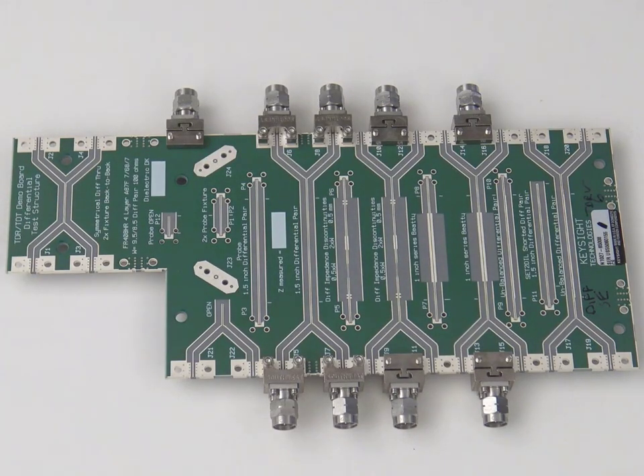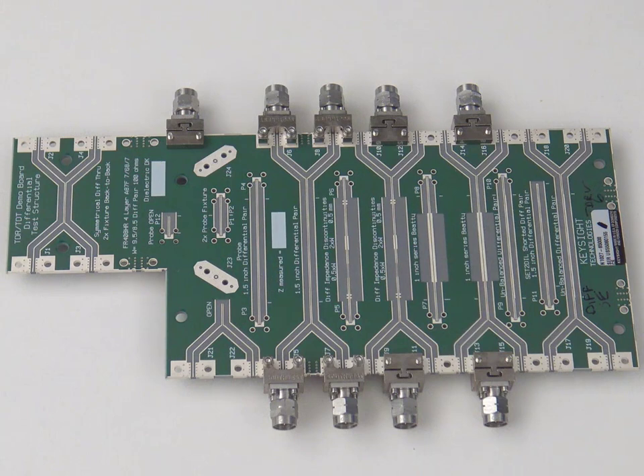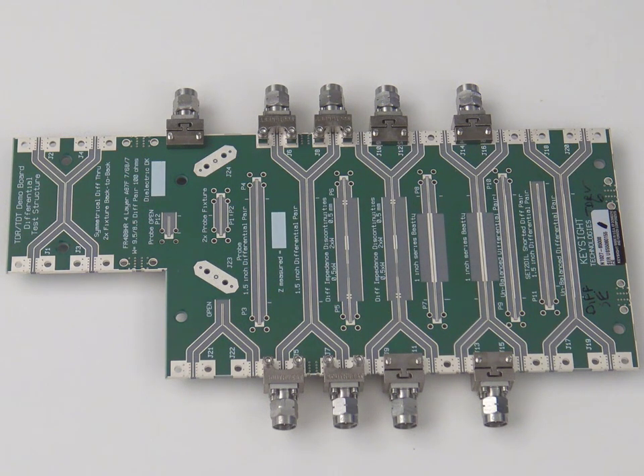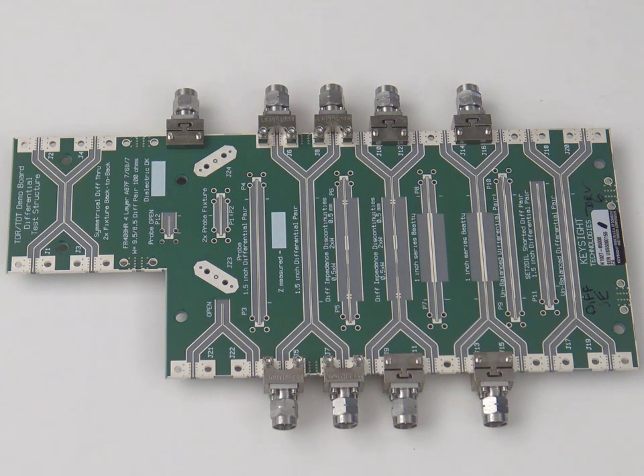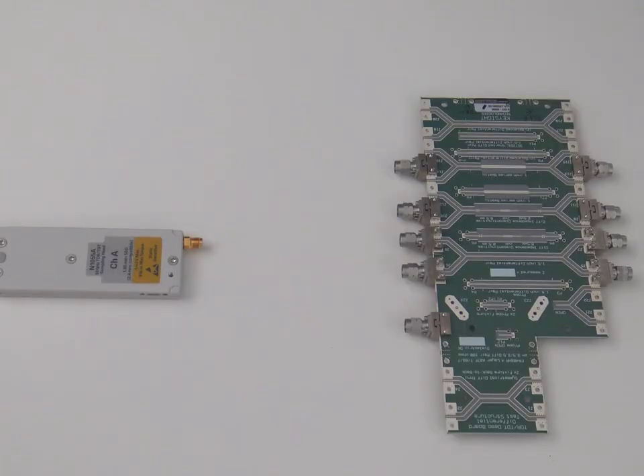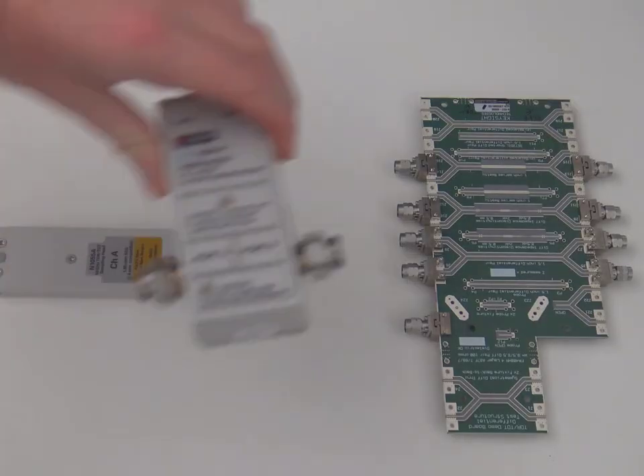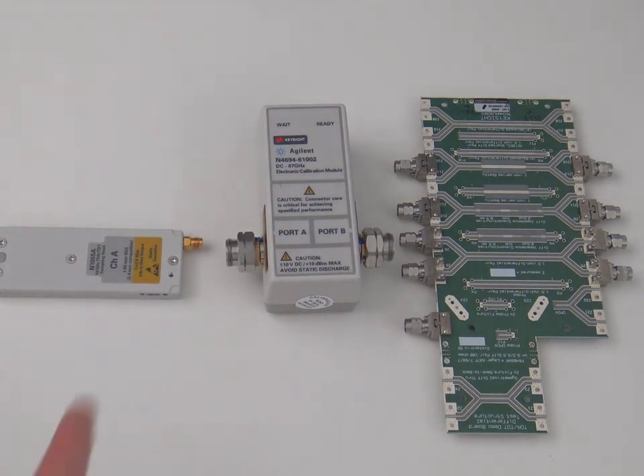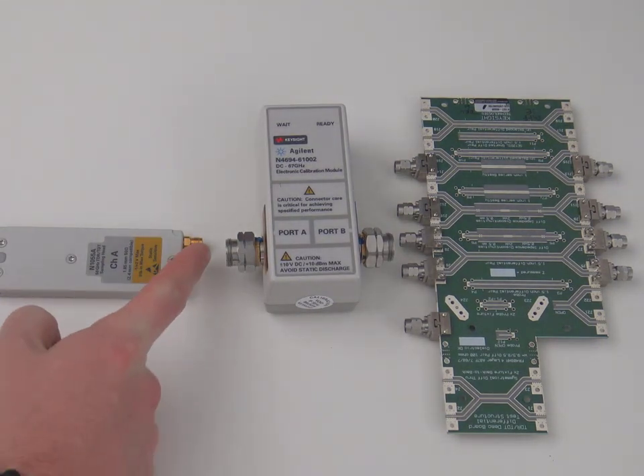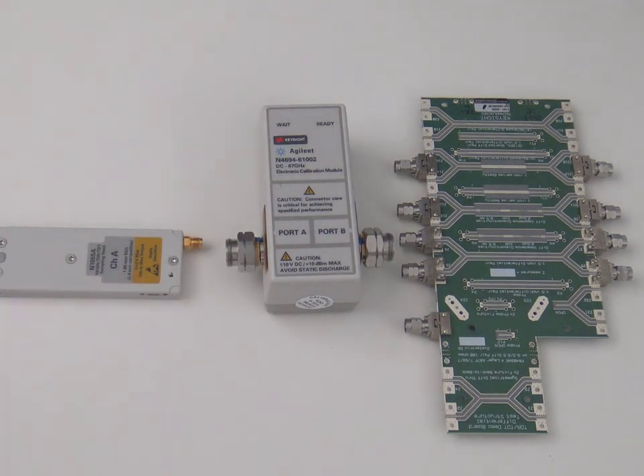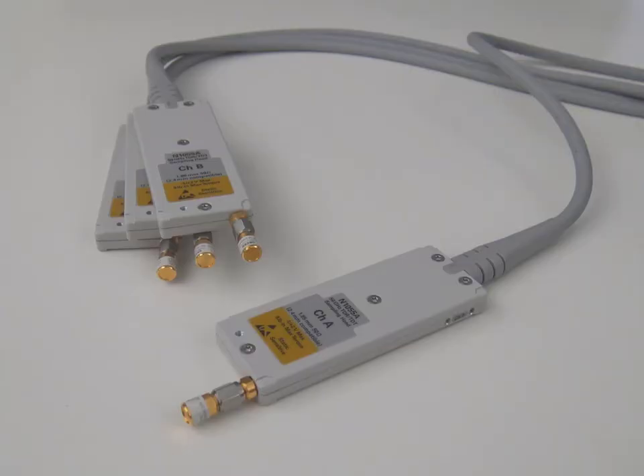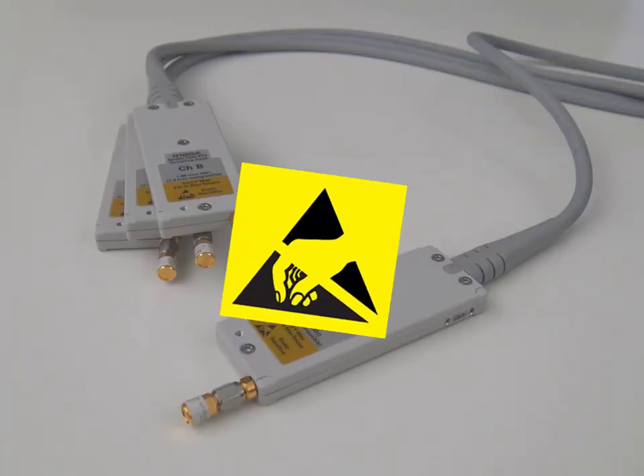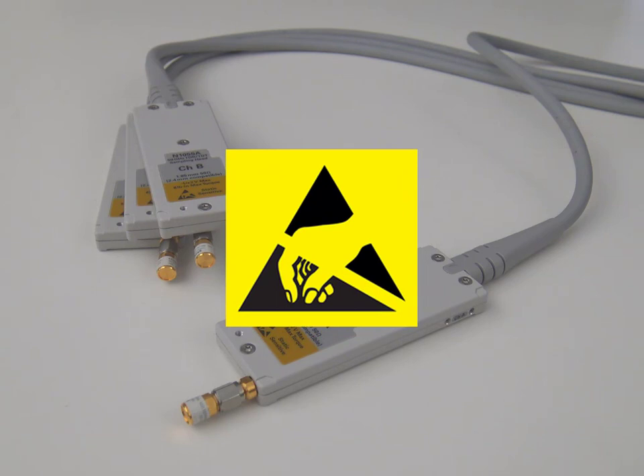Here we have an unknown device that we'd like to test using time domain reflectometry. To make sure we are measuring only the device and no other cables or adapters, we will use an eCal to bring the measurement plane right up to the mate point on our TDR heads. Remember to follow all ESD precautions as the measurement heads are ESD sensitive.